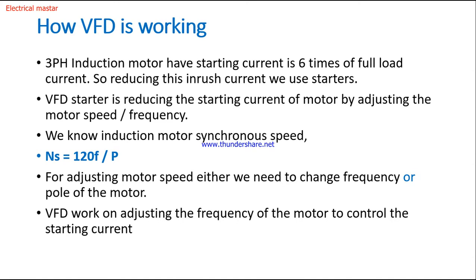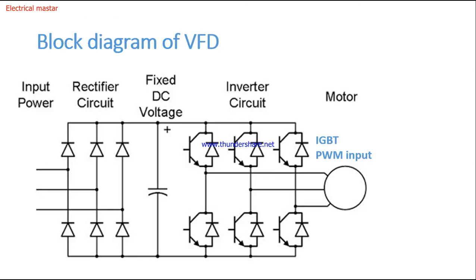The detailed working of VFD can be understood from the block diagram. There are three parts involved: rectification, filtering, and the inverting circuit. Normal AC power is connected to the rectification part. The bridge rectifier converts AC into DC, which is then connected to the filters, because the rectified DC is not pure — it is combined with noise and harmonics.